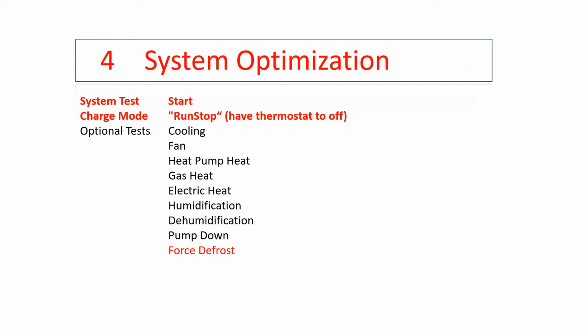Right now we don't have a droop setting in the system, so if you want to run backup, it has to be done in here, or you have to wait for a delay, a time period over which the home loses temperature before the backup comes on. We can also force defrost here. Keep in mind when you go to an optional test and force defrost, you're accelerating the timing of the 30, 60, 90, 120. So you still have to have a coil under 32 degrees.